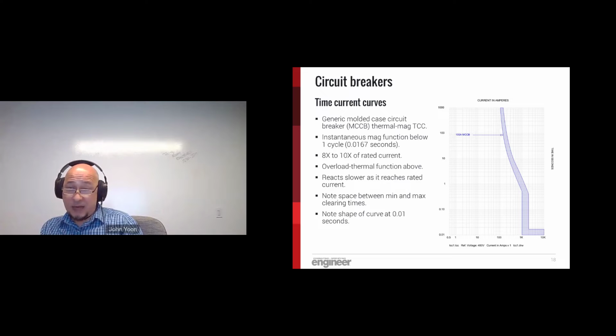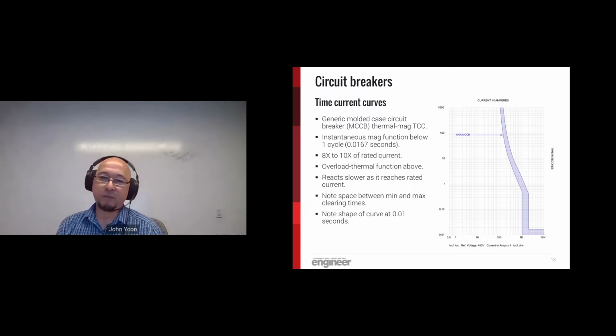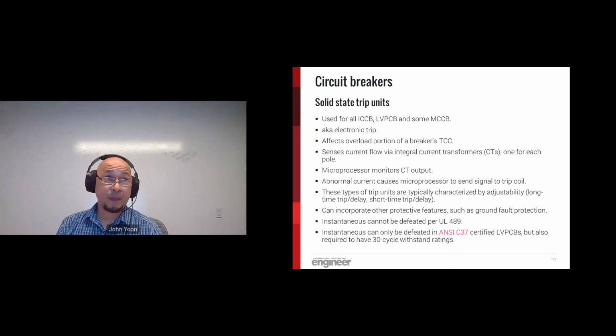Finally, at the base of the time current curve, we see that instead of a smooth curve at the bottom, we have a weird dog leg at extremely high current. Basically, a level of current that you would typically expect with something like a bolted fault. You can see that it responds extremely fast. Again, half to one full cycle, but that blue area extends out to the right. Now we have a certain level of uncertainty. All UL 489 breakers have this characteristic dog leg in the instantaneous region, which can become a selective coordination issue. With some types of solid state trip units for circuit breakers, you can adjust the pickup setting, but if the breaker is UL listed under 489, it cannot be defeated, only adjusted. Again, the equipment downstream of this that you're trying to protect with these breakers is typically only rated for 3 full cycles of fault current. Moving on.